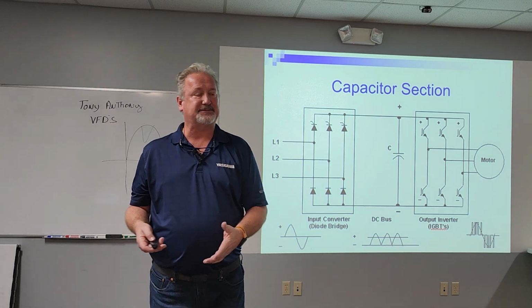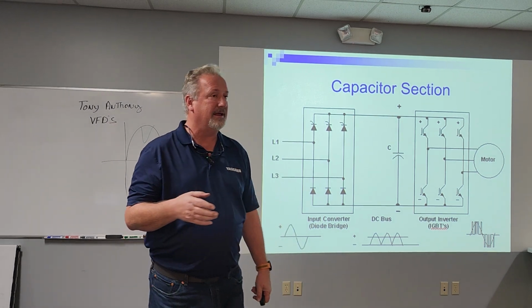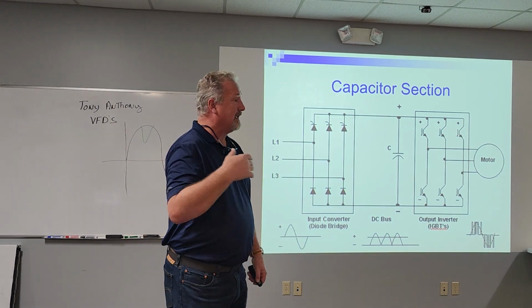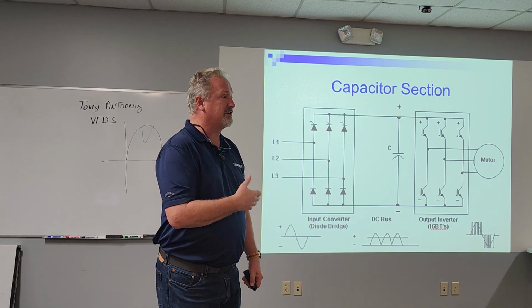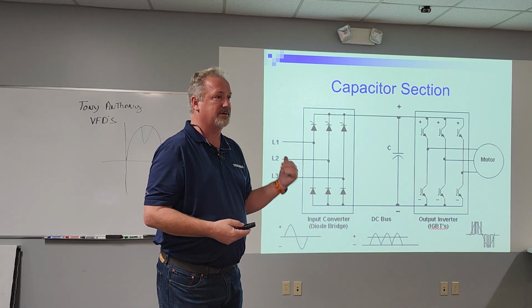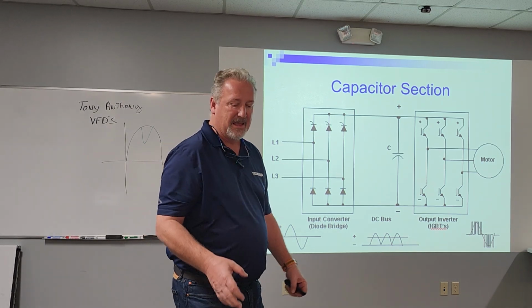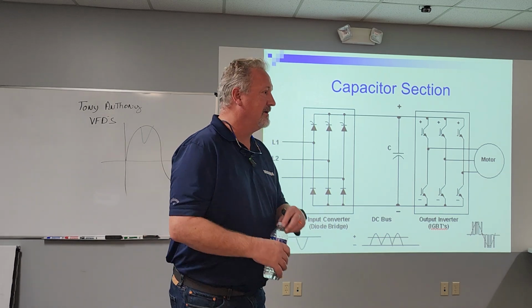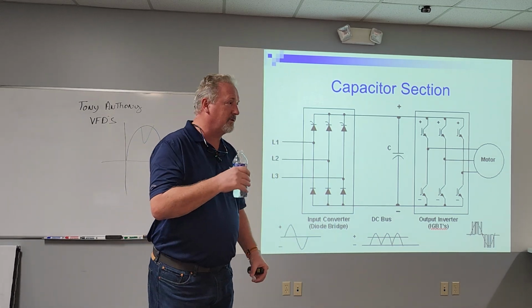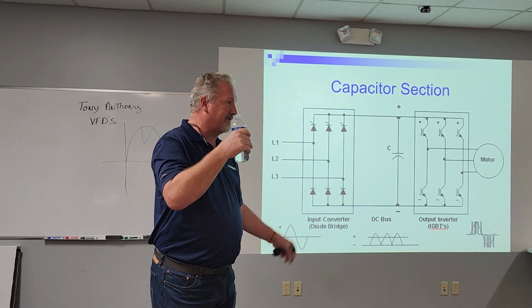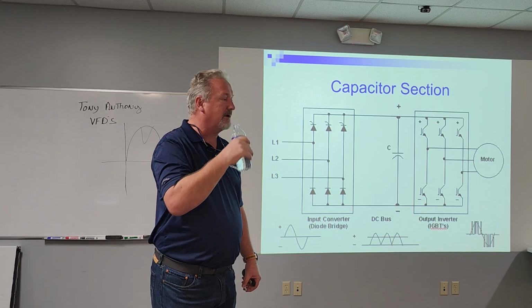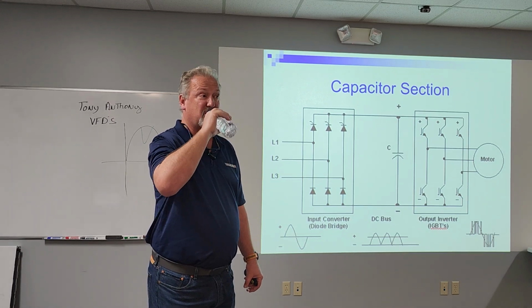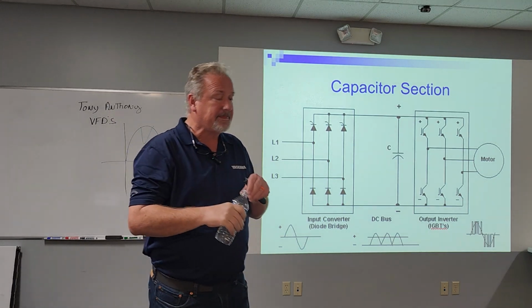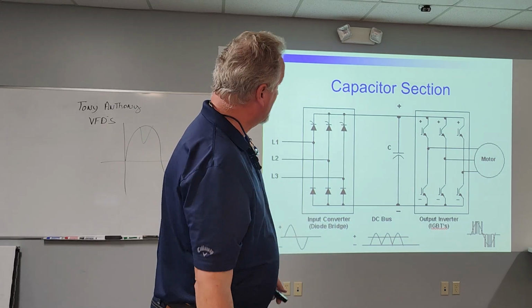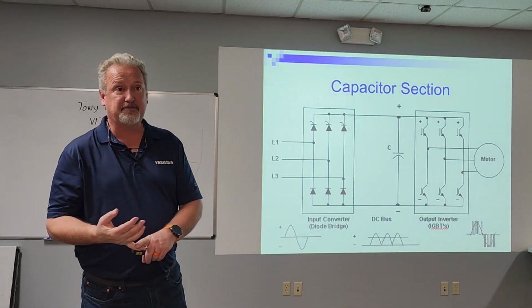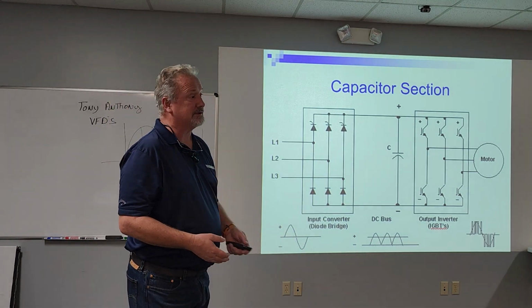Your DC bus should be, and this is a good little troubleshooting tool, if you think you have a problem with your DC bus, it should be about 1.44 times your input voltage. So if you have 460 in, multiply that times 1.44, and you'll be in the 675 volt range, somewhere around there. That's what your DC bus should be. If it's not, you probably either have a problem with your incoming power, or a problem with your diode bridge.